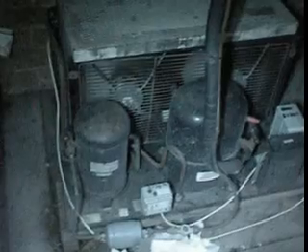Last fridge to clean — so far so good, much better. I'm done with these two units; they are working, but not very well. If we look above them — I'm going to be in for it on these ones. That's probably the worst I've seen so far without pulling the cover off. The filters have been cleaned but the coils are pretty dirty. That was a good bit of work — well, that took me just under three hours. Everything came up beautiful, works well. I'll be back there again in about a month or two.